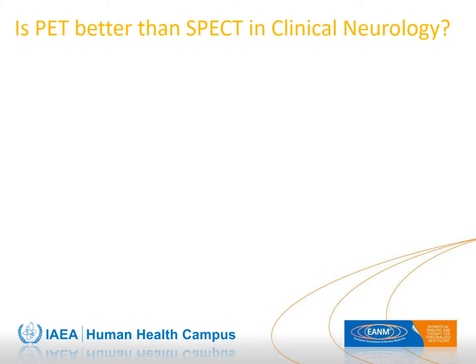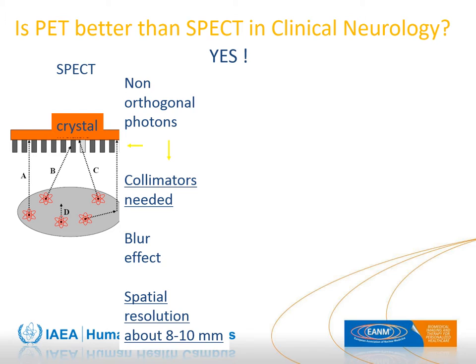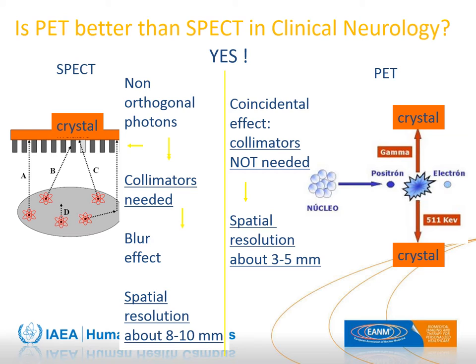Both PET and SPECT can be used for these purposes, but is PET technically better than SPECT in clinical neurology? The answer is yes. The collimator in a gamma camera is made of lead or tungsten and rejects many photons, resulting in SPECT sensitivity being several orders of magnitude lower than PET. Furthermore, the spatial resolution of SPECT is about 8–10 mm, while PET achieves about 3–5 mm, making PET superior in clinical neurology.